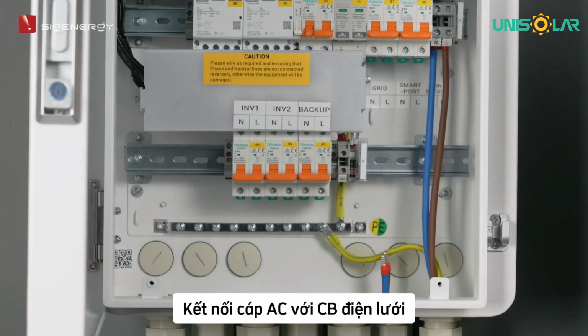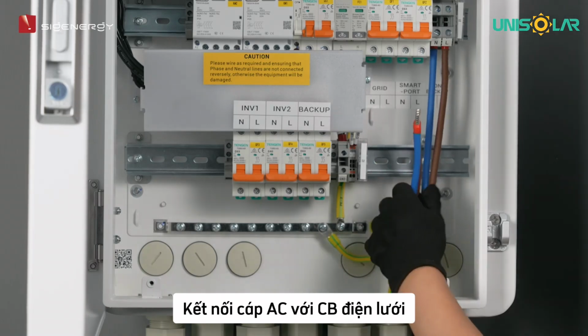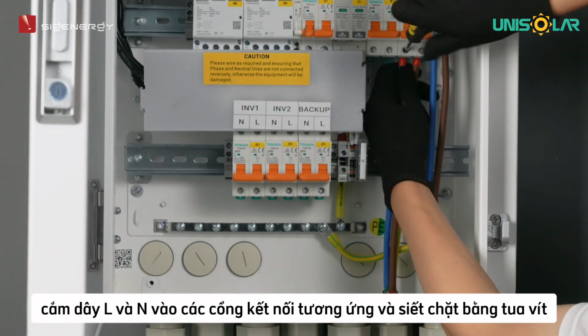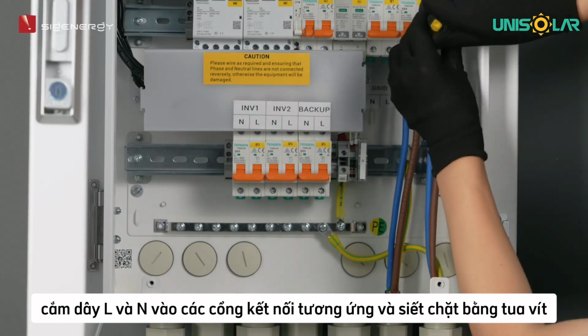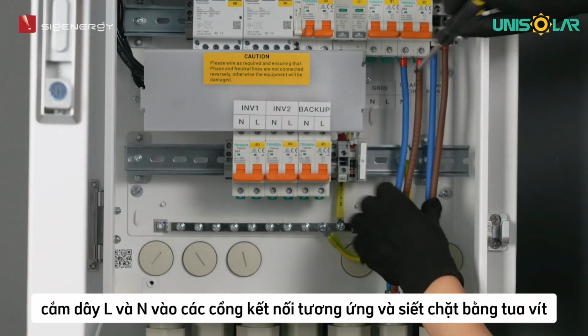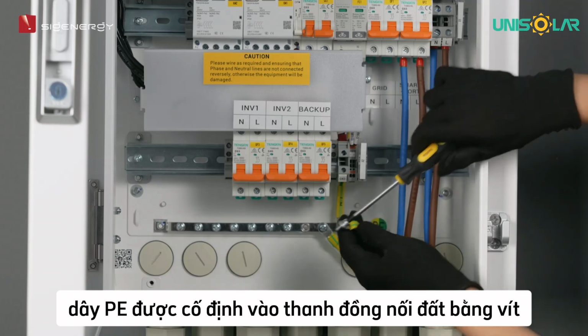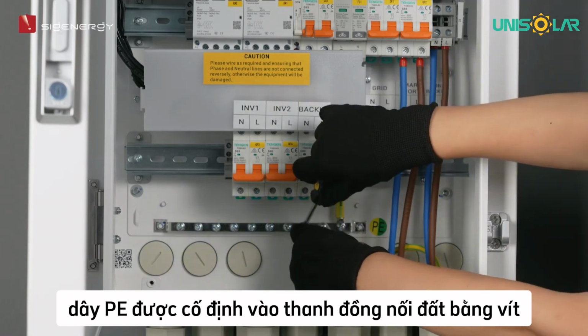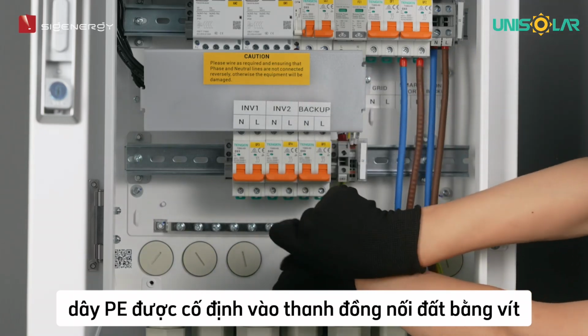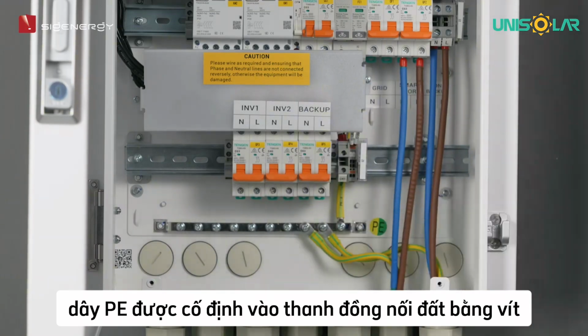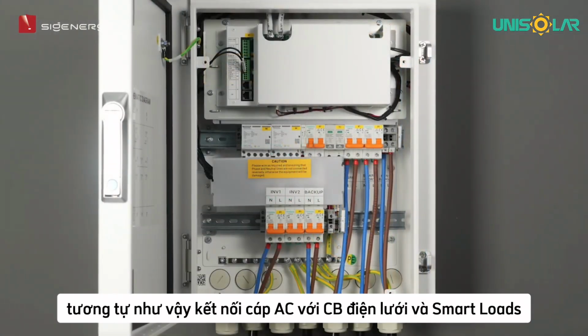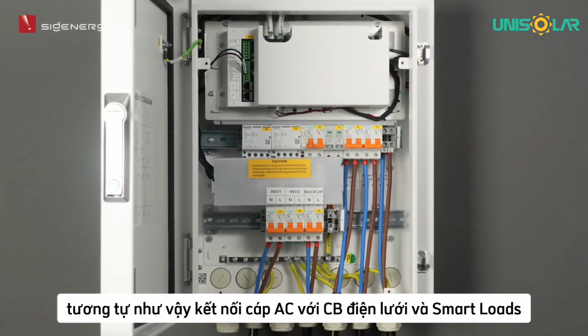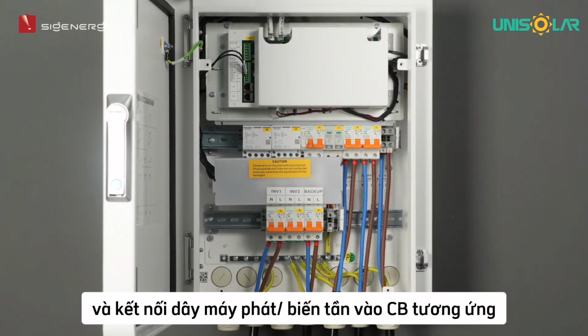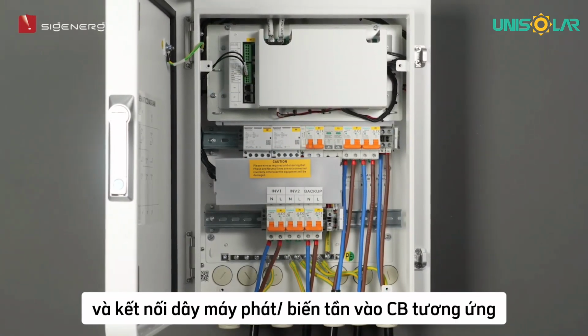Connecting grid side AC cable. Insert the L and N wires into the corresponding ports and tighten them with a screwdriver. The PE wire is fixed to the grounding copper bus bar with screws. Similarly, connect the AC cables on the backup and smart load, generator, inverter side to the corresponding breakers.